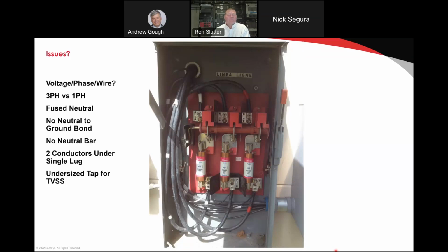Okay, I have another question. You were talking about surge producers. Can you provide a few more examples of surge producers? I'm thinking of satellite dishes or chain link fences. So the basic concept that I was referring to is called zoning, which is producers, absorbers, non-isolated, and isolated. And the producers are things like an isolated ground bar, right? So basically your equipment goes into your isolated ground, feeds back to your MGB, that's a producer. An example of an absorber would be the ground ring itself, a water main, the building steel, all of your main ground points.